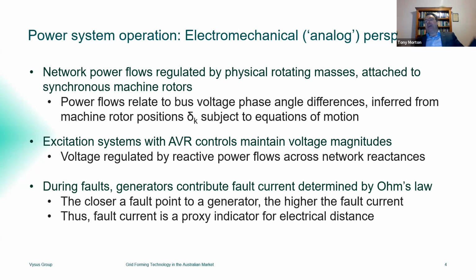And then on top of that, we have excitation systems that are regulating the voltage magnitudes, which are to a certain extent decoupled from what's happening with those power flows. And then when you have a fault in the network, of course, we see a fault current contribution from each of those machines, which is essentially determined by Ohm's law.